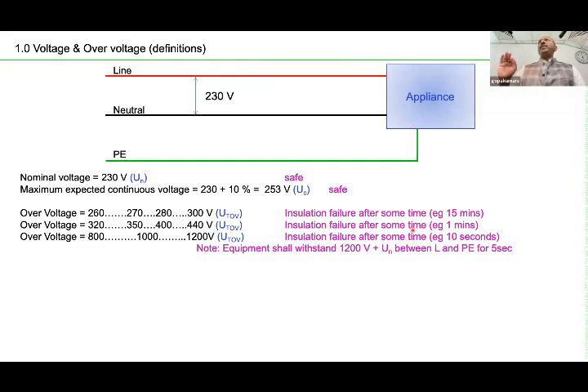One of the tests made mandatory in IEC is line to earth. Every equipment, line to earth, must be able to withstand 1200 plus UN, meaning 230 volt, so 1430 volt, for up to 5 seconds. This is a mandatory test required for every equipment, between line to earth or neutral to earth. That means the basic insulation is tested at 1200 volt for 5 seconds. Very important.